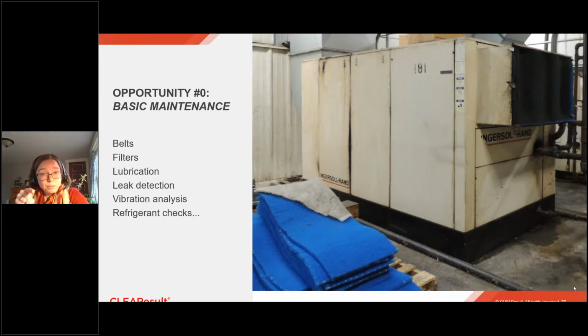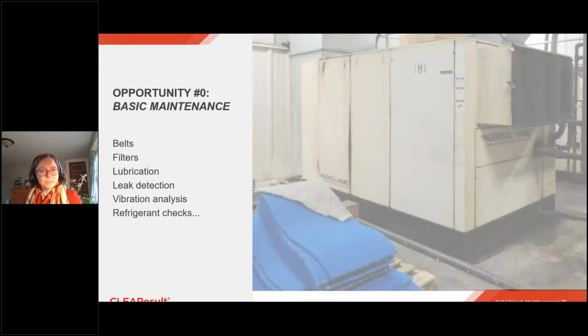Now this picture I have up here, I have here because look at it. That's an air-cooled compressor that has one of the filthiest intake filters I'd seen in a long time. And you see the pile of fresh filters right there. Would have taken somebody like 30 seconds to change it. It's right there, and they hadn't. So why? Frederick, if you can click a couple times.